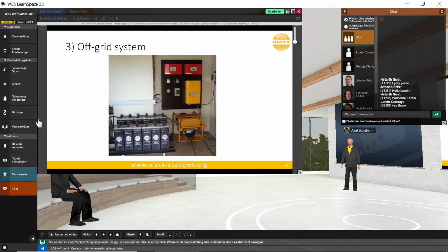Here are your solar inverters at the top that convert your solar and put that also onto the grid on the AC side. So it's exactly what I've shown you there. And then you've got probably a petrol generator, not a diesel generator, because it looks like a 2 or 3 kilowatt unit. So that is really an off-grid system in its smallest form.